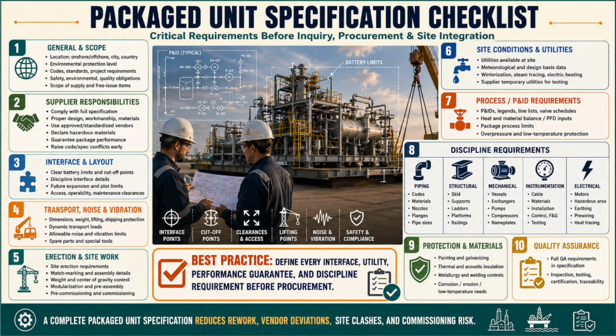Layout requirements must also be explicit. State plot limitations, equipment spacing, access routes, escape paths, maintenance clearances, valve accessibility, instrument visibility, and possible future expansion. A tightly packed skid may reduce vendor fabrication cost, but create decades of operating difficulty. Design for the technician who must remove a motor, calibrate a transmitter, pull a heat exchanger bundle, or operate a manual valve during an emergency. If the equipment cannot be safely reached, the package is not well designed.